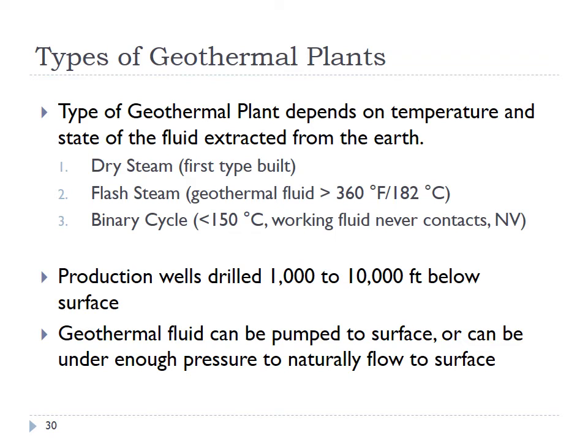In the third case, the working fluid never contacts the geothermal resource. That's typically done when you have temperatures below 150 degrees C, where flashing doesn't really make much sense. You can't get much pressure out from flashing.